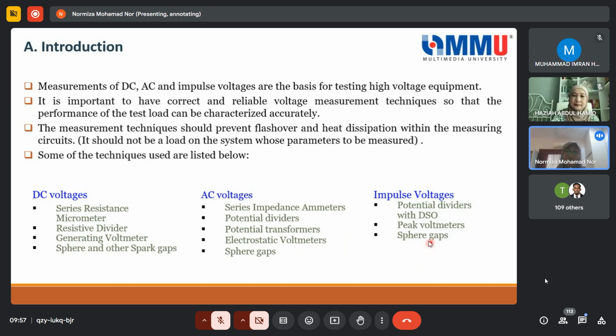So you can see that some of this equipment, like the potential divider, can be used for all. It means that if the high voltage lab buys one potential divider, it can still be used for all kinds of voltages. But certain equipment can only measure certain types, such as the generating voltmeter. We don't use it for the impulse. This should just be for the DC voltages.